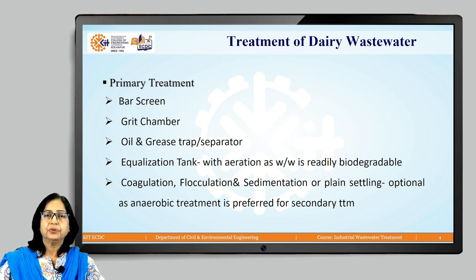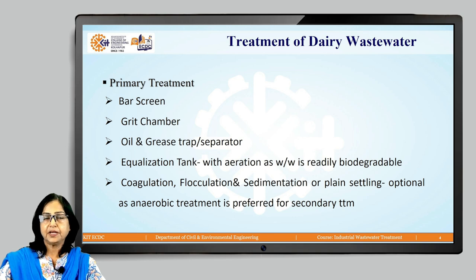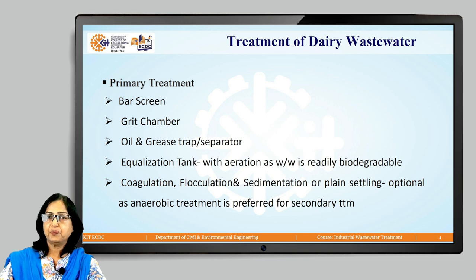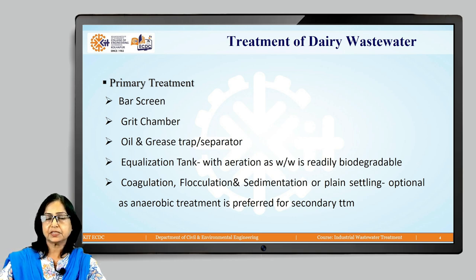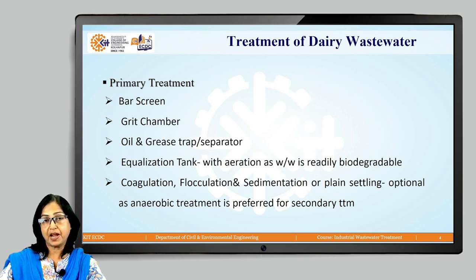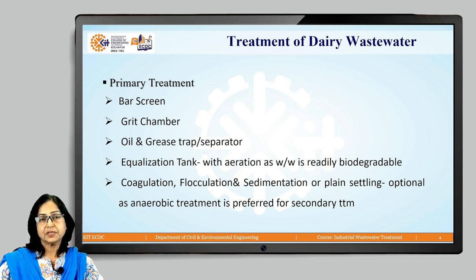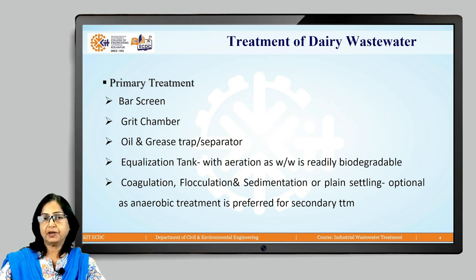The characteristics of dairy wastewater include high BOD, COD, TDS, suspended solids, and oil and grease, so it requires both primary and secondary treatment. Primary treatment consists of a bar screen followed by a grit chamber to remove settleable heavy inorganic solids, followed by an oil and grease trap or separator. Since dairy wastewater contains a high amount of oil and grease (fat), its removal is essential.